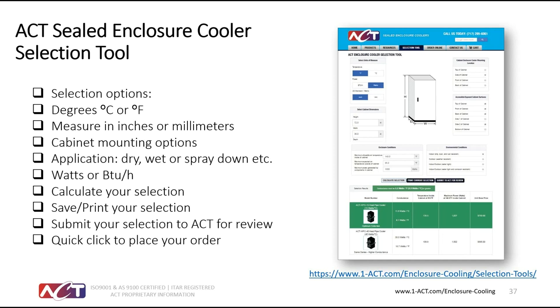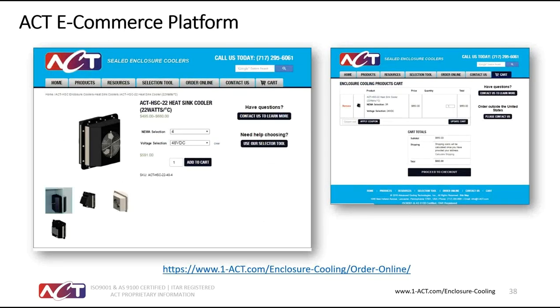And then you put in the size of your cabinet and what the expected internal heat load is, and then what the maximum allowable temperature is for your application on the inside and what you would expect to see on the outside of the cabinet. And once you select that, you just hit a very simple calculate button. And if there's a solution, it'll actually highlight the best choice in green, which you can kind of see there, which is a little tough. But from there, that choice can then be clicked on and selected by price or size.